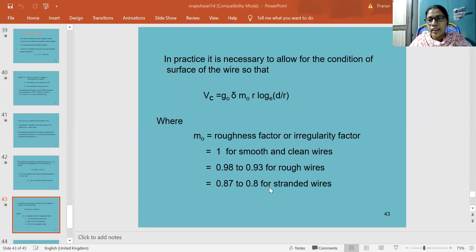And delta is the density of the air surrounding the conductor, which is equal to 3.92 b by 273 plus T, where b is the pressure in centimeters of mercury, small r is the radius of the conductor in centimeters, and d is the distance between the conductors in centimeters. Therefore, Vc is equal to 21.2 m naught delta r log of capital d by r kilovolts RMS to neutral. This is the critical disruptive voltage.